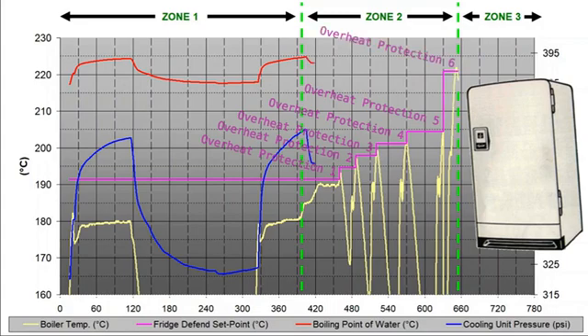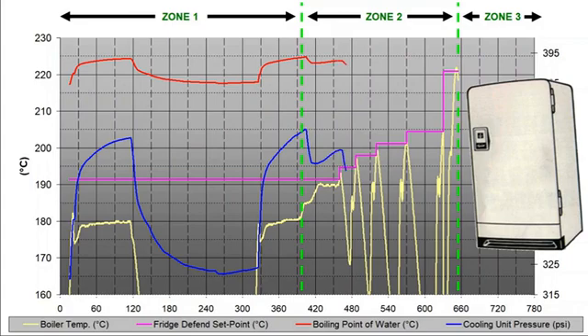Next we show the cooling unit pressure along with the boiling point of water curves. Please take note of the boiler temperature rising with each successive Fridge Defend overheat protection event. By the sixth time that the Fridge Defend takes action to protect the fridge, observe that the boiler temperature has not risen to the boiling point of the water in the cooling unit.